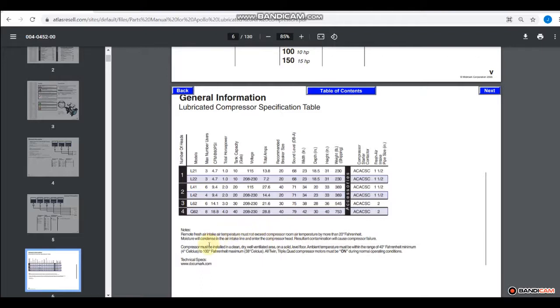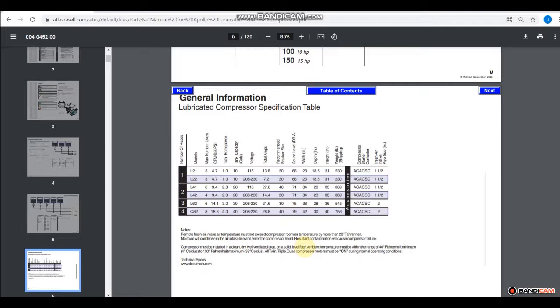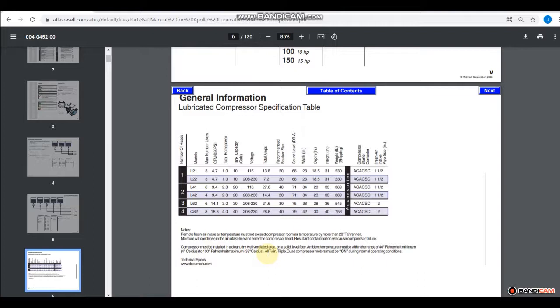The other thing is the compressor must be installed in a clean, dry, and well-ventilated area on a solid level floor. We've seen it all. You have to be sure you put your compressor into a good environment. Ambient temperature must be between 40 and 100. So it can't be below freezing and it can't be super hot. The twin, triple, or quadruple compressor must be under normal operating conditions.